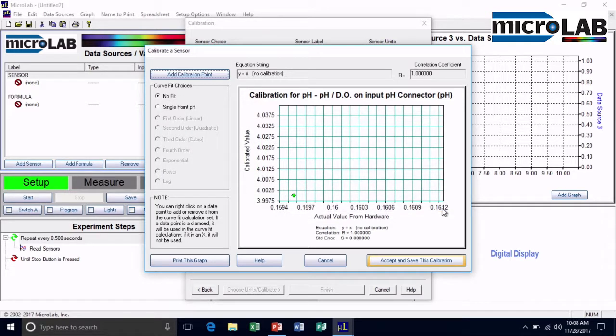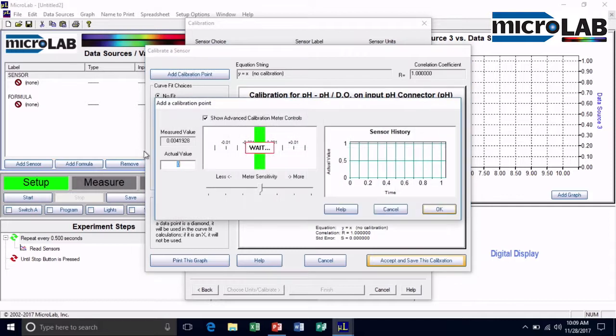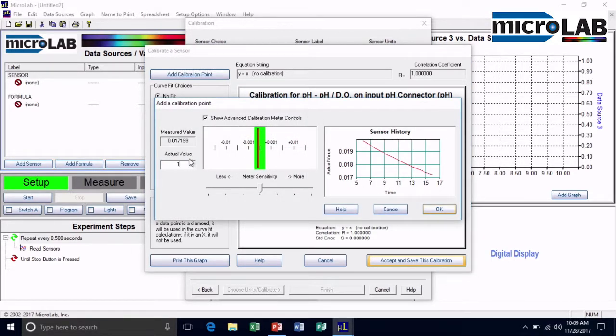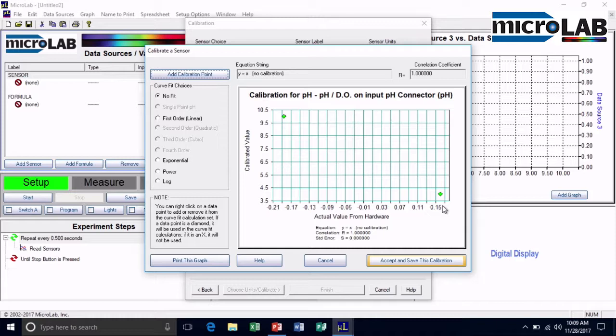I'm going to take the sensor out. Let's add another calibration point. This one, I've got pH 10 buffer. So I'll say 10.0. And if you notice, boy, it really shifted. It went way down. Actually, this one equilibrated very rapidly. So I'm going to take that and say, okay, I like that data point. Got it. And I will put the pH electrode back in the buffer. And I have 2 data points, one at pH 10 and one at pH 4.